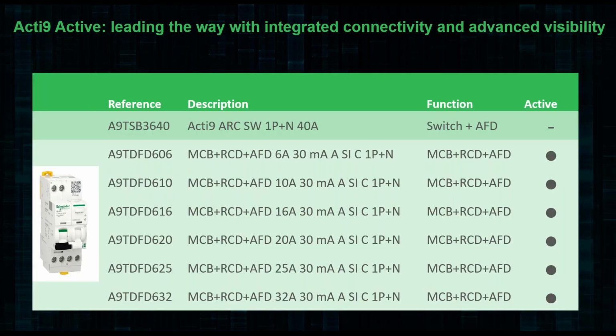The system itself comprises 6 active devices. So we've got individual type devices for each of the ratings, whether it's 6 amp, 10 amp, 16, 20, 25, and 32. And these are active and connected devices. We do have one at the top, which is just an arc fault detection device that reaches ratings of 40 amp, but that's not a connected device at the moment.